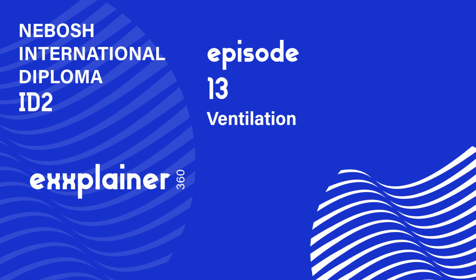You can't filter those with a bag. No. For gases and vapors, you usually need a different approach. Sometimes it's destruction, basically. You incinerate them, burn them off safely. Or you use tower scrubbers, where the contaminated air bubbles up through a column of water or a chemical solution that absorbs or reacts with the contaminant. Washing the air? Essentially, yes. Or there's recovery. This often uses filters filled with activated charcoal. The charcoal adsorbs the vapor molecules onto its surface. Sometimes you can even recover that solvent for reuse.